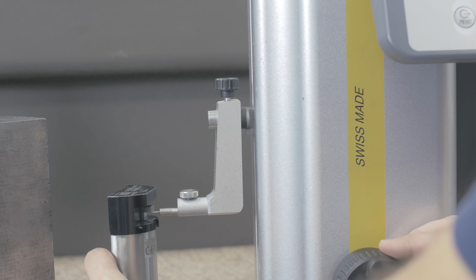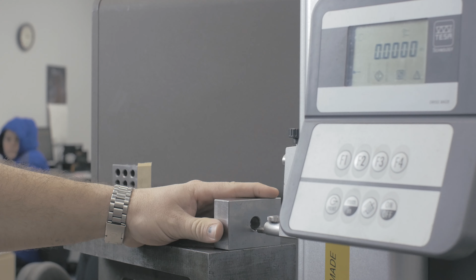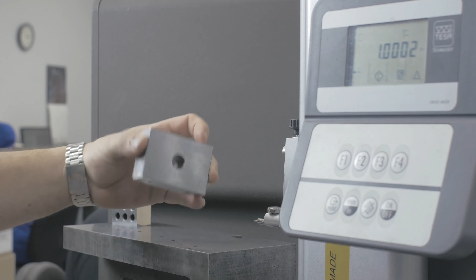Press F2 again and touch the tip 2 times to the measure from point, or on the top and bottom of the area you're measuring if you need the 0 point between 2 planes. This will establish a 0 that your measurements will come from. Once the 0 is established, measure the distance by touching the probe to the desired feature until it beeps. 2 touch-offs are required to display the measurement.